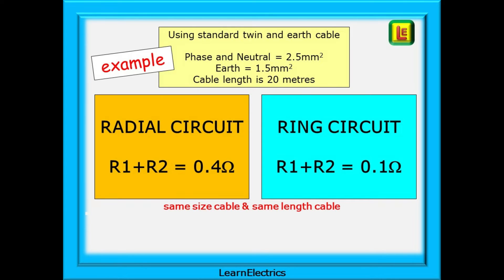In the examples, the phase and neutral are both 2.5mm copper and the earth or CPC is 1.5mm copper. When we measured R1 plus R2 for the radial circuit, we had a resistance value of 0.4 ohms. For the ring circuit — the same length, the same size cable — the resistance was just 0.1 ohms.